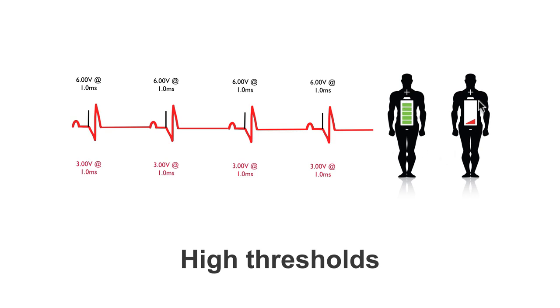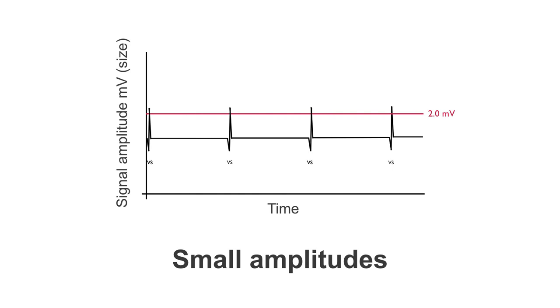Ultimately, their device will not last as long, and in their lifetime they will end up having more surgeries to replace their pacemaker. The other issue of small signal amplitudes can be seen here. We have some ventricular complexes, but they're very small — only just over two millivolts, which is where our ventricular channel's sensitivity is set to.